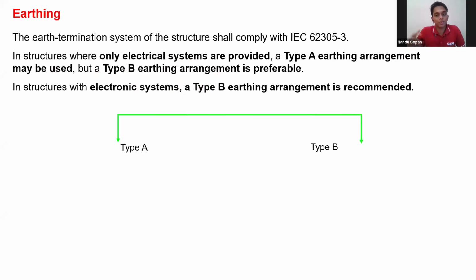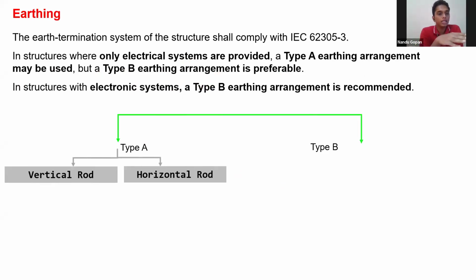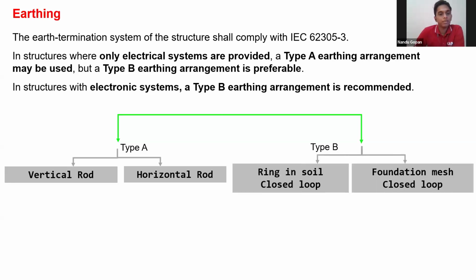So what is type A and type B earthing arrangement? Type A means vertical and horizontal rods - you can go outside and check that there are a lot of earth pits, and all those earth pits are type A earthing, vertical rods. Type B means a ring in soil - if you have a ring or a foundation mesh in the soil, it is type B. It is a closed loop.